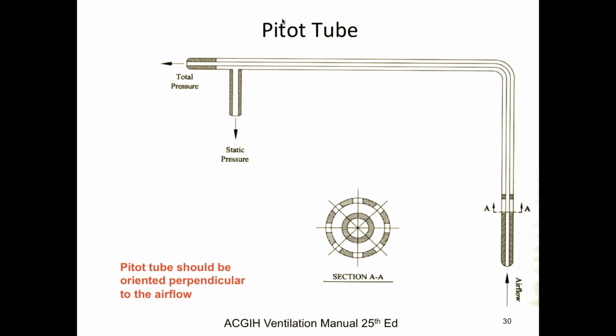So the air is moving this way. It's not feeling the velocity pressure. What's that measuring? Static. That's static pressure, exactly. So I have total pressure, and this is measuring static pressure. So one's measuring total pressure, one's measuring static pressure. If I take total pressure and subtract the static pressure, what am I left with? The velocity pressure. The velocity pressure tells you how fast the air is moving.